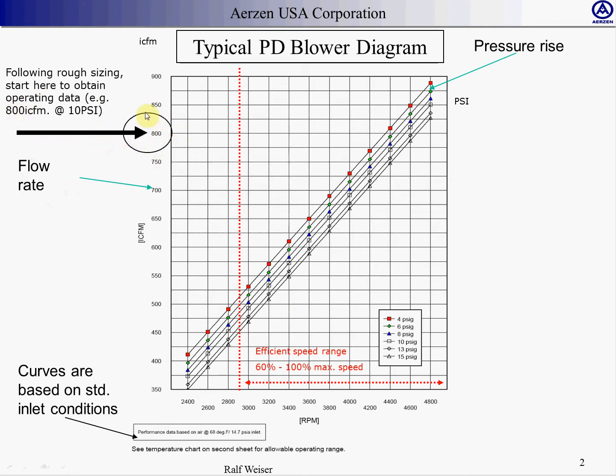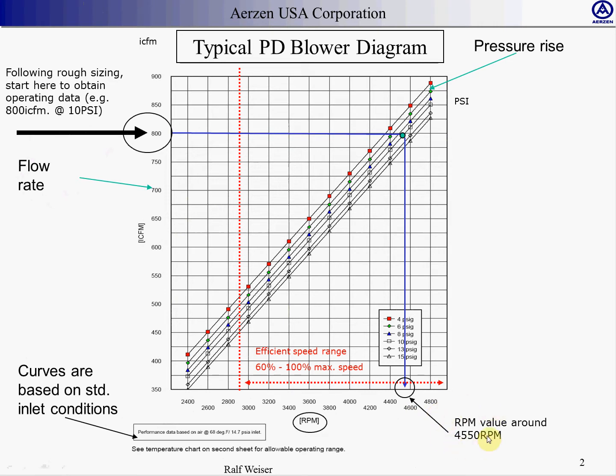Once you know what flow you want, you draw a straight line over to the pressure rise of 10 psi in this particular case. If it were any different, pick any of these pressure curves based on this legend. Mark the spot where the line of my 10 psi and my flow line cross, and then draw a vertical line all the way down to the RPM. Here you have roughly 4,500–5,000 RPM with this particular machine.